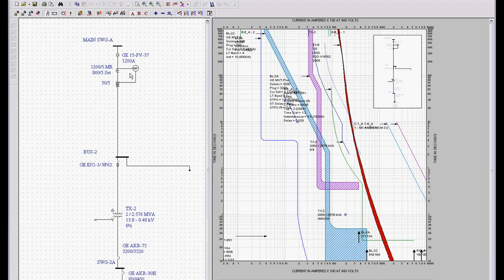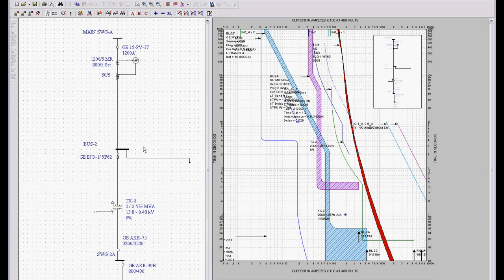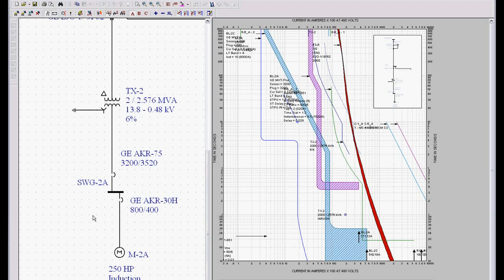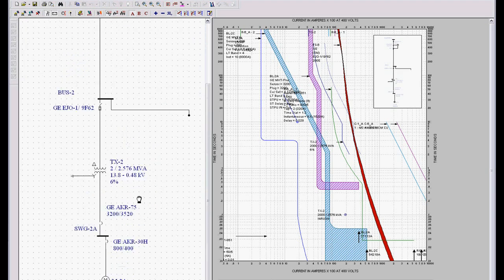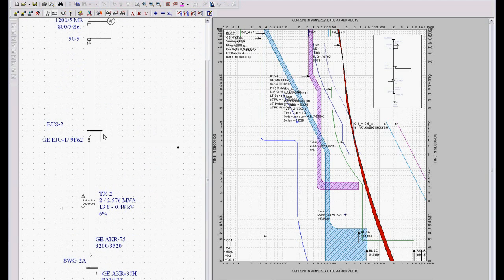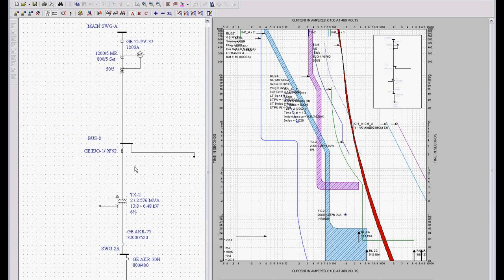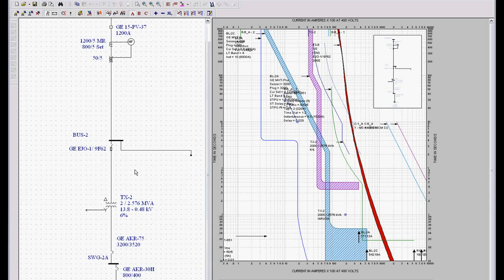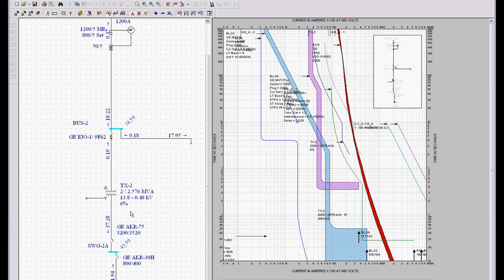Now what I want you to see on this is the one line that we're looking at over here on the left hand side. Remember the other motor control center contributions from this switchgear lineup? They are still there. You're just not looking at them on the one line. The daisy chain transformer is still here. It has contributions and back feeds to this system. So the entire network model is perfectly intact. It's still part of this system so that when I hit this short circuit button, all my short circuit currents are identical to the main network system because it is. We're just looking at a different view.